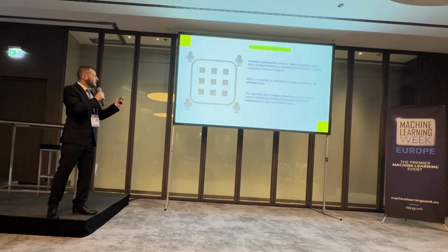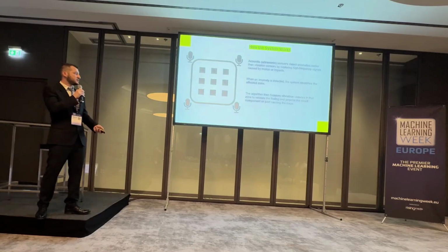So by separating this square box into 4 parts, each acoustic sensor is responsible for 1/4 of the machine. What it means is, let's say this acoustic sensor detects an anomaly. This means it is responsible for these 5 vibration sensors. In the beginning, because we had only the vibration sensor, it cost 800 per month, because we were receiving data at a 200 millisecond frequency, and that was very costly.